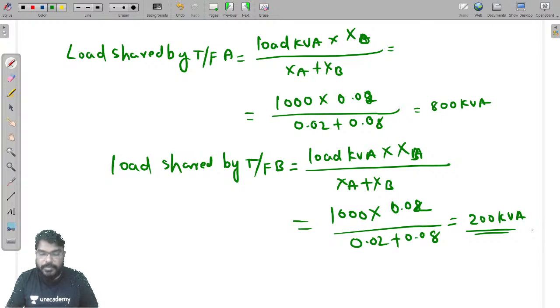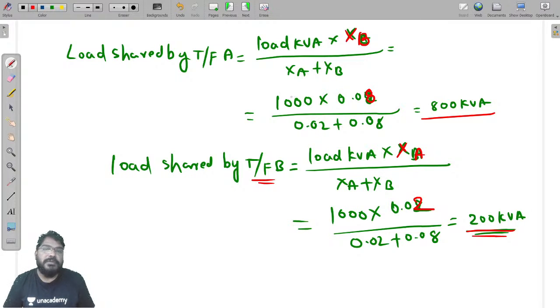Load shared by transformer A is equal to load kVA into XB divided by XA, and load shared by transformer B is equal to load kVA into XA, where XA is 0.02 and XB is 0.08. Calculate to get 800 kVA and 200 kVA - one transformer is operated in the rated condition, another one is under-rated condition.